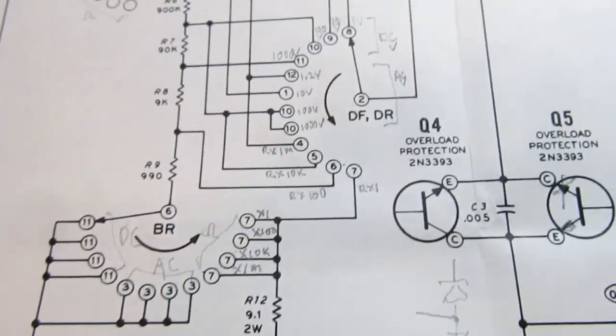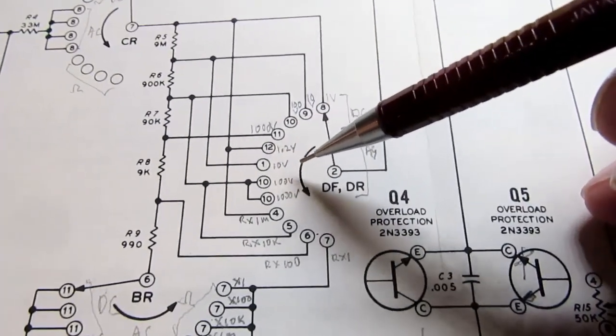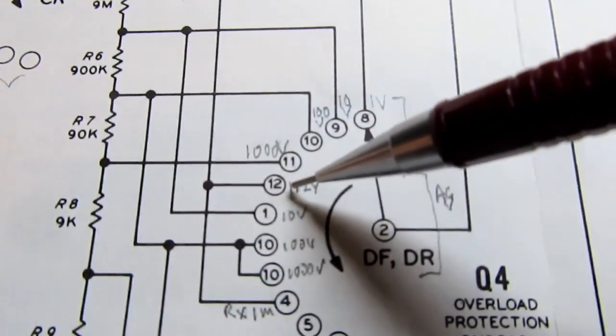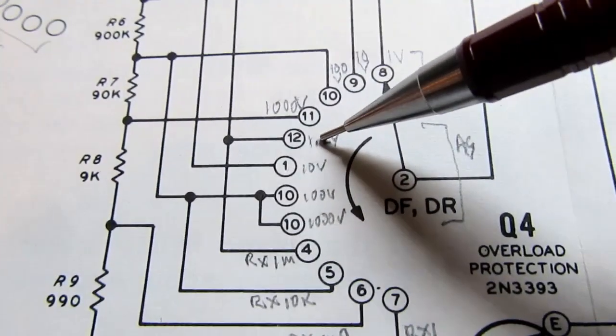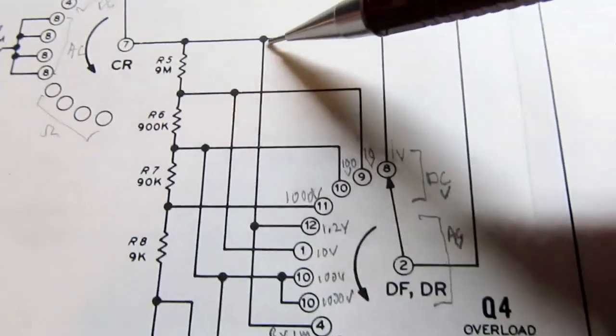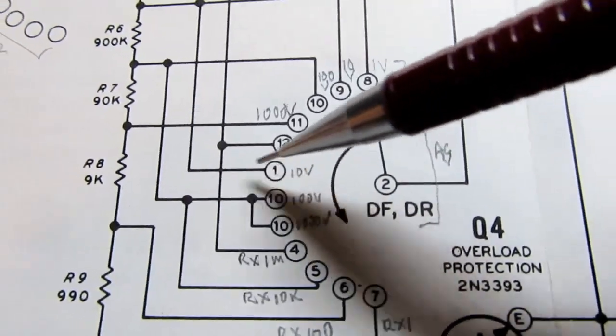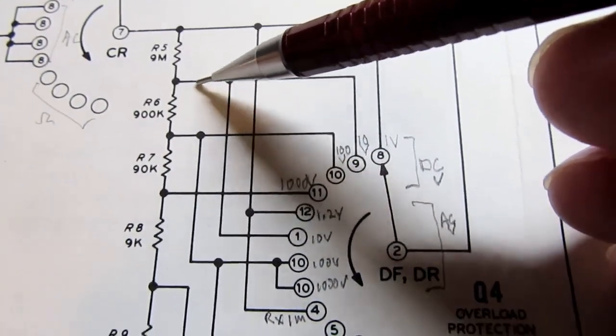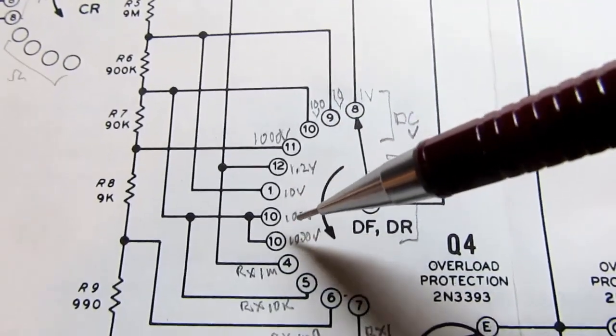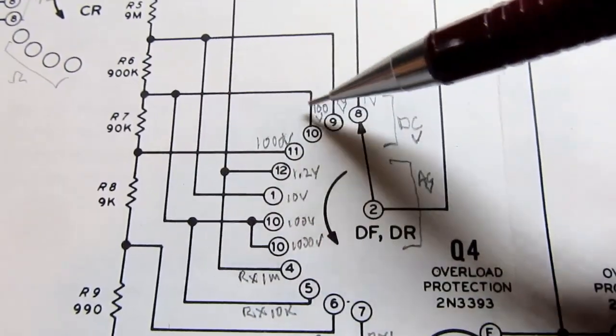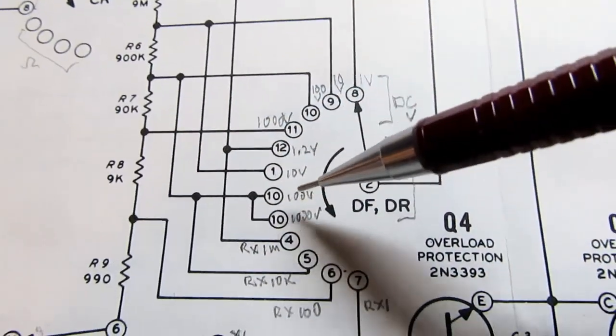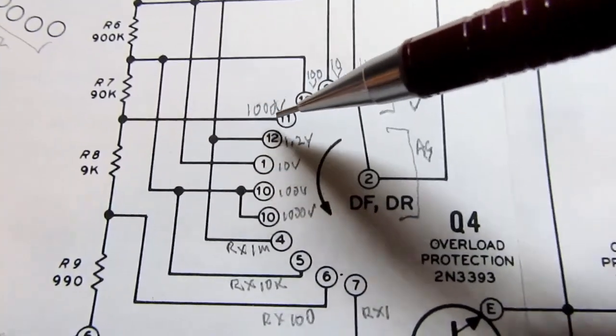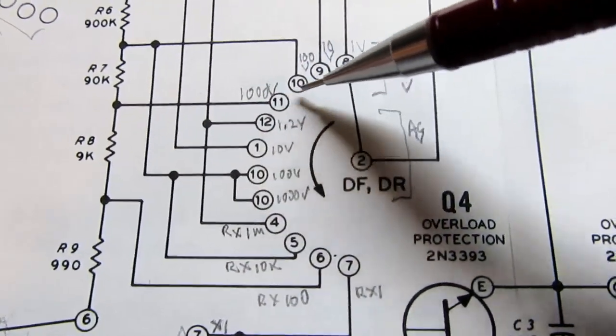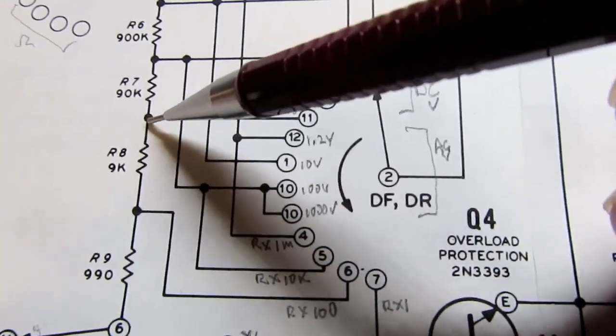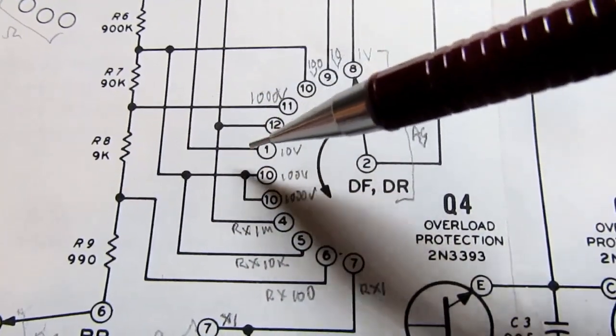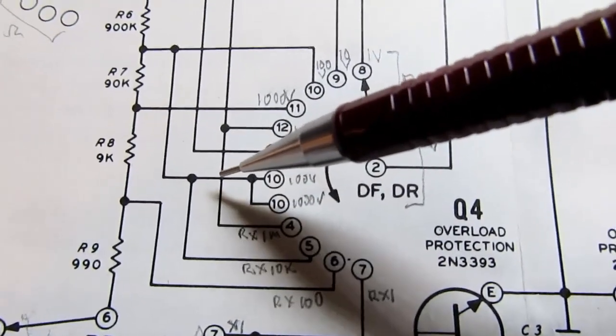Let's look at what happens over here. If you're in the lowest range, it's not 1 volt, it's 1.2 volts. And that comes right off the top of the divider. The 10 volt comes off of the same place it does for 10 volts on DC. The 100 volts comes off the same place it did for that. And the 1000 volts, however, does not.